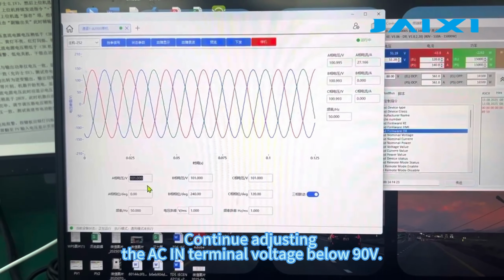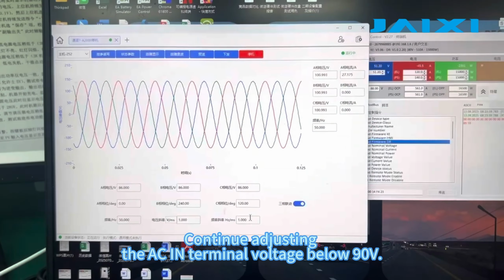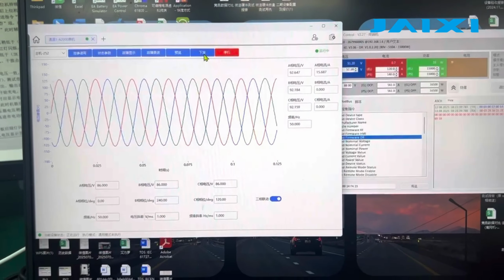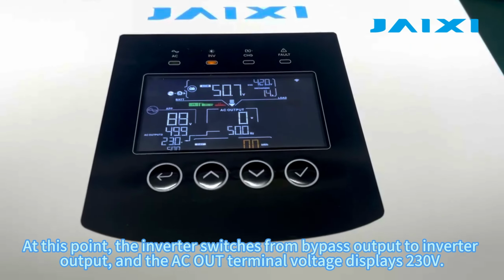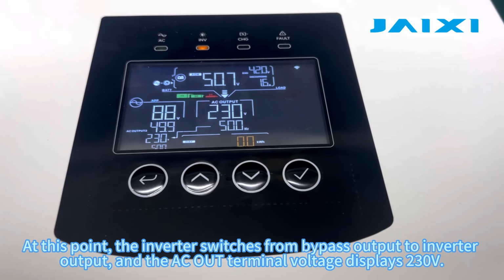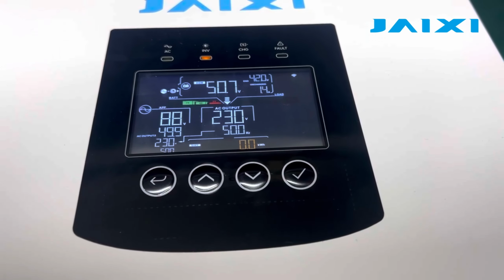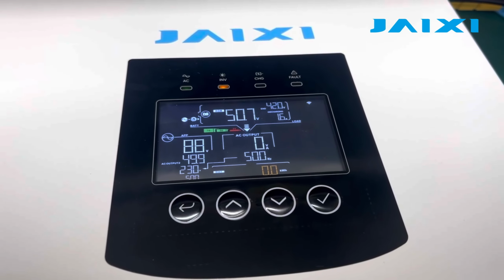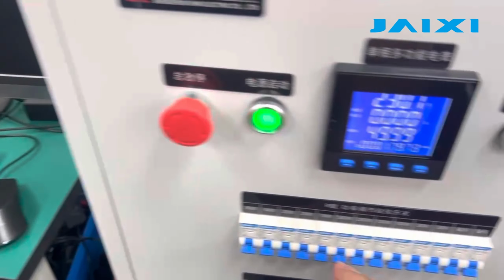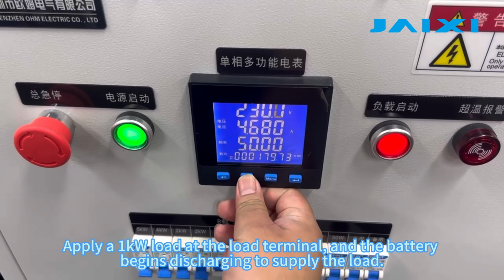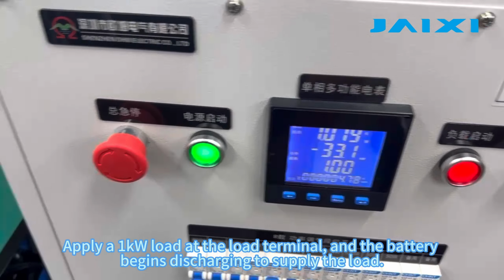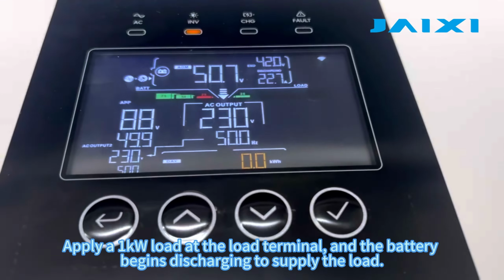Continue adjusting the AC in terminal voltage below 90 volts. At this point, the inverter switches from bypass output to inverter output, and the AC out terminal voltage displays 230 volts. Apply a 1 kilowatt load at the load terminal, and the battery begins discharging to supply the load.